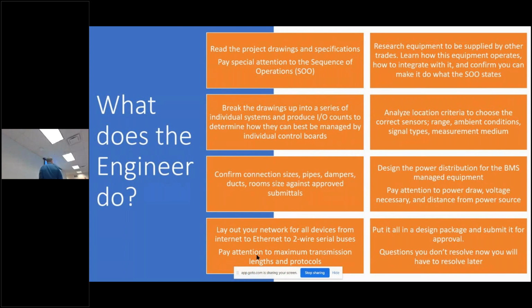Same thing for outputs. How many outputs do I have? How many pumps do I have to turn on? How many fans? How many lights? How many damper actuators do I have to modulate? Fans, valves, etc. So you create your I/O count, and that helps you generate a list, roughly, of how many controllers you're going to need in your system.